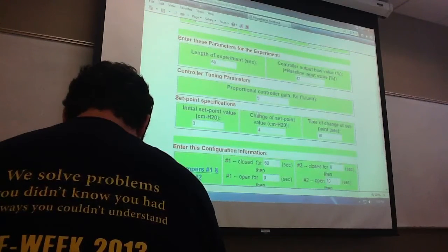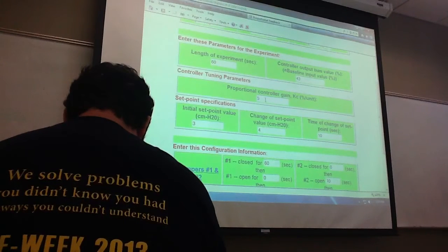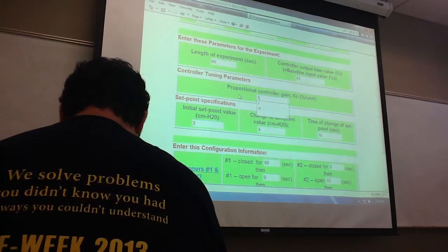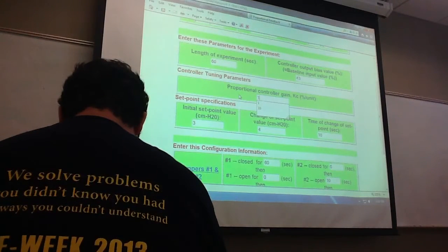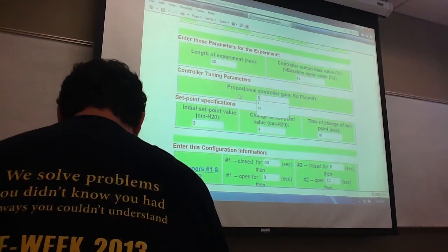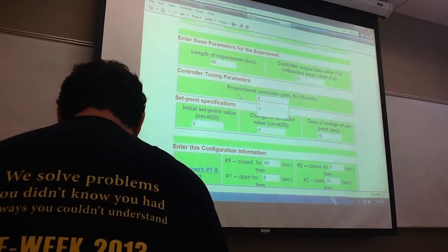All right, and this gain? 1.1. How about 1? That works. One significant digit on tuning parameters. That means K sub C and later on tau sub I. One significant digit, no more. Anything more is a waste of time and energy, and confusing.